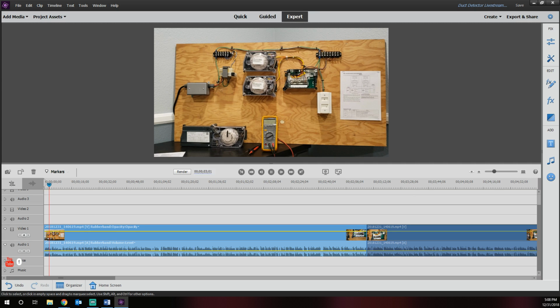I've got a duct smoke detector set up, and I have it set up so that we can simulate trouble conditions or alarm conditions, and I just want to explain the difference. The trouble condition is an instance where, depending on the detector, this particular detector, I can set it up to initiate a trouble condition if you were to remove this cover. So let's say someone was doing work on the duct detector and they left the cover off. It would initiate a trouble condition, which would tell the...